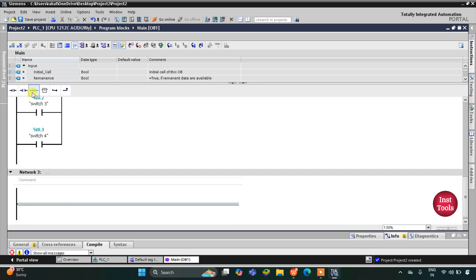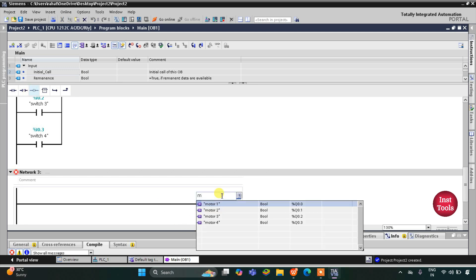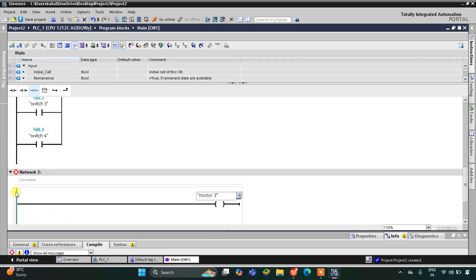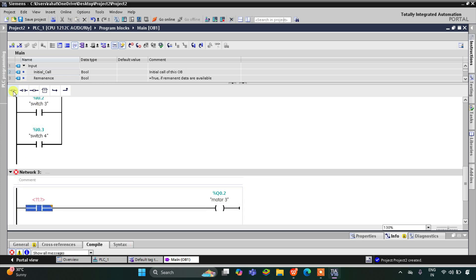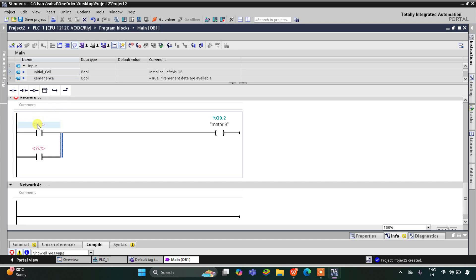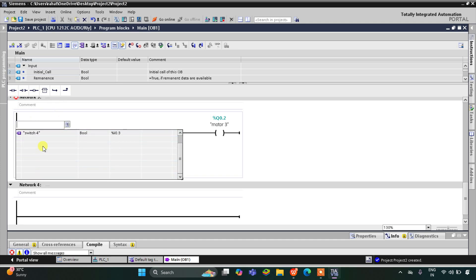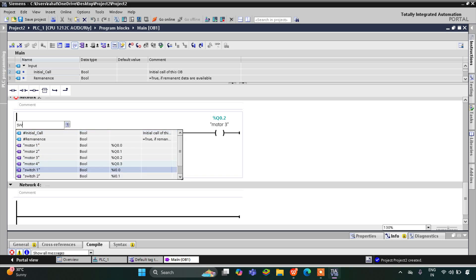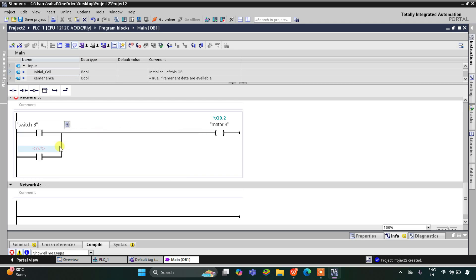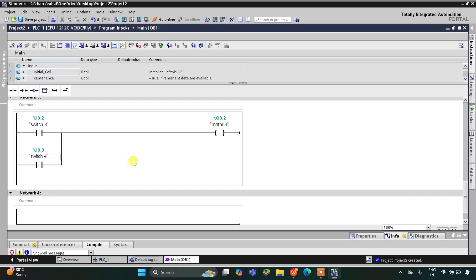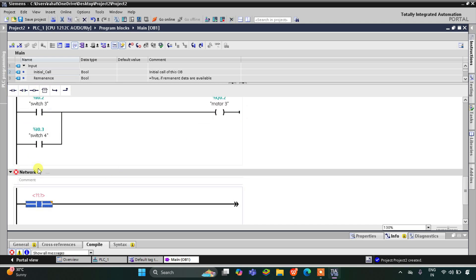For motor 3, I'll insert a coil and add a normally open contact, then open a branch with one more normally open contact and close the branch. The addresses will be switch 3 and switch 4 — so if switch 3 or switch 4 is on, motor 3 will be on. For motor 4, only switch 4 turns it on, so I use only one normally open contact assigned to switch 4, with the coil assigned as motor 4.